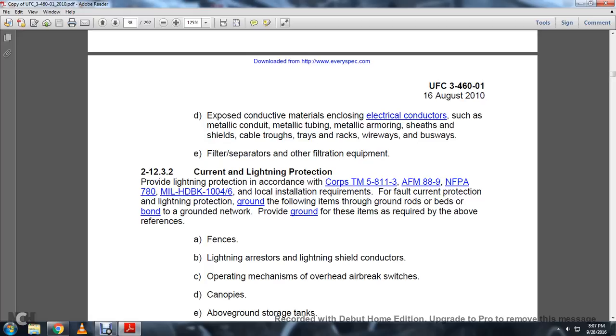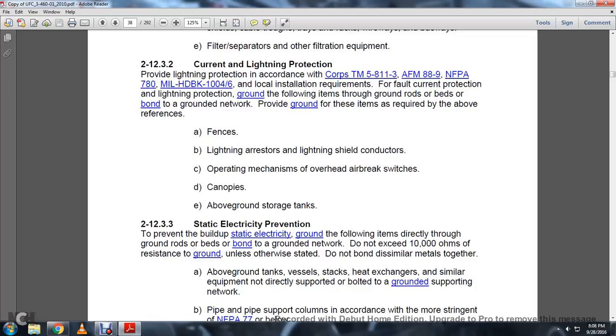212.3.2 Lightning protection. Provide lightning protection in accordance with Corps TM 5-811-3, AFM 88-9, NFPA 780, and Military Handbook 1004/6, and the installation requirements for fault current protection and lightning protection. Ground the following items through ground rods or beds bonded with the ground network, provided that these items are required by the above references: fencing, lightning resistors, lightning arresters, lightning shields or conductors, operating mechanisms, overhead air brake switches, canopies, and aboveground storage tanks.